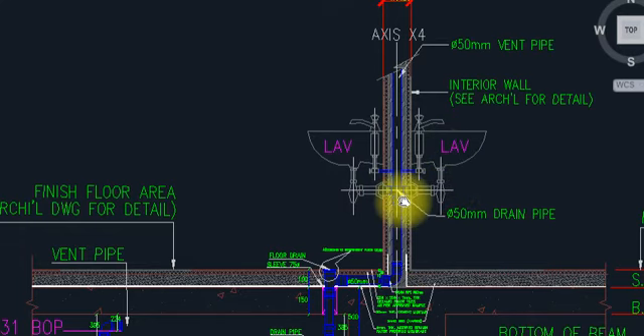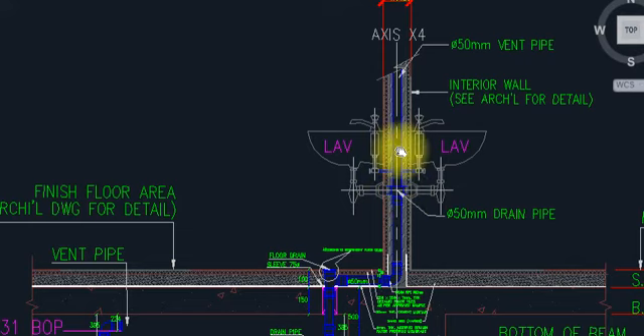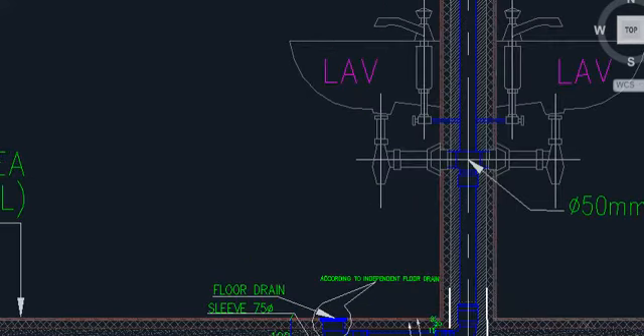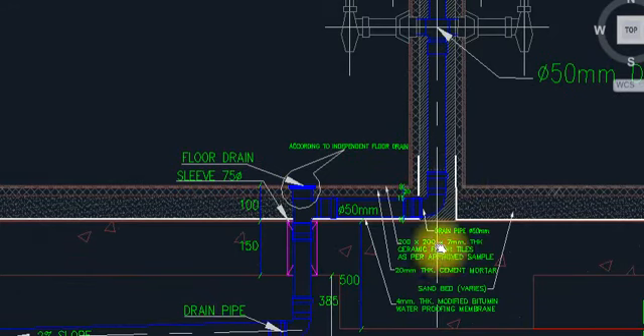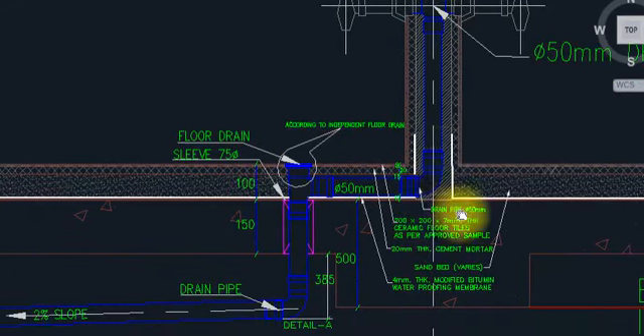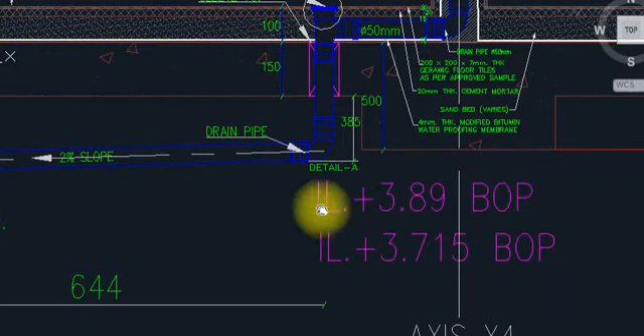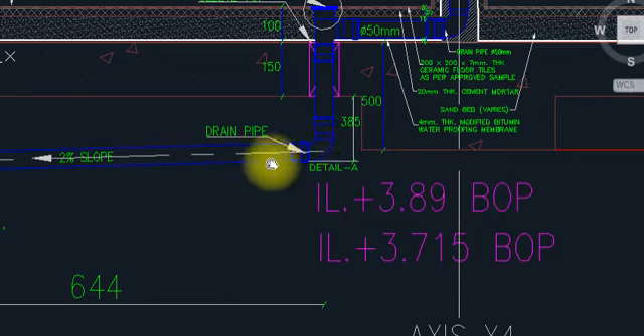This is a lavatory or wash basin. A 50mm drain pipe is coming here, and it will go here. We are compulsorily providing a clean-out — a floor drain to clean-out like that. This is the detail for tiles and everything. This is the drain pipe, 50mm. This is our invert level — the bottom of pipe invert level above.